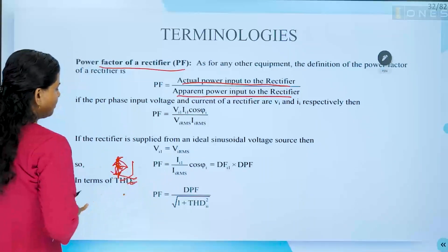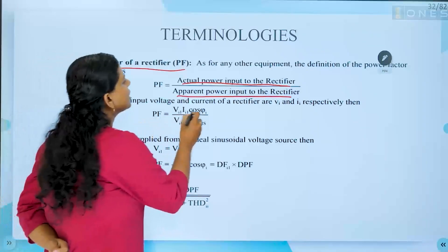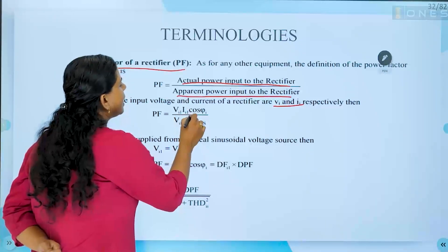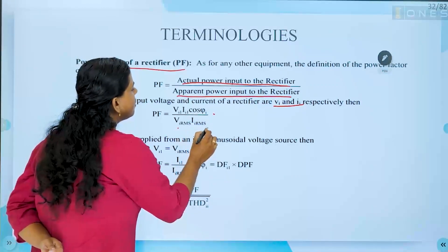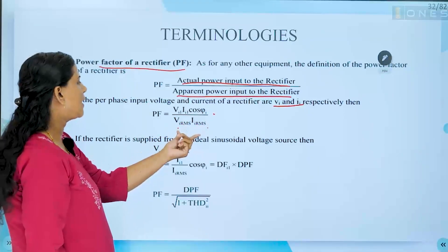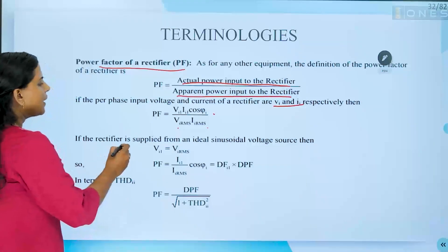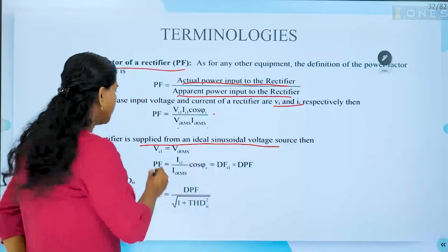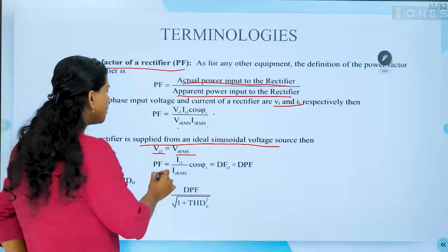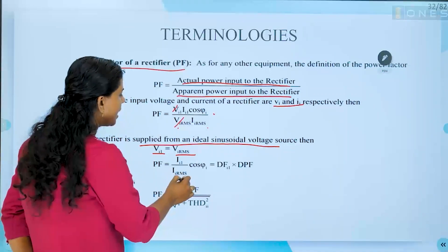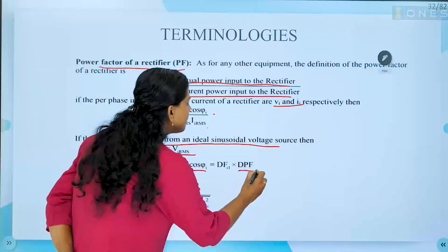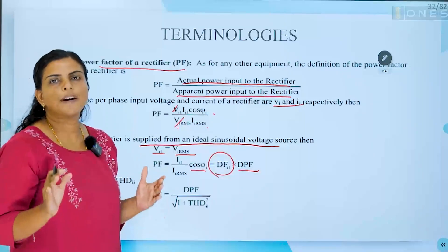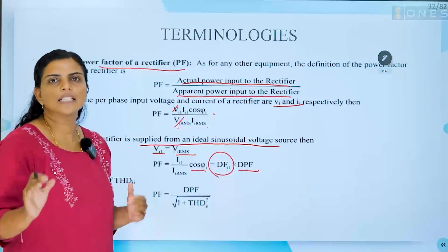Power factor indicates the useful power index. If the RMS input voltage and current of a rectifier are Vi and Ii respectively, then power factor equals (Vi1 · Ii1 · cos φi) divided by (Vi,RMS · Ii,RMS). If the rectifier is supplied from an ideal sinusoidal voltage source, the RMS value equals the fundamental value, so Vi,RMS = Vi1. The equation reduces to: power factor equals (Ii1 / Ii,RMS) · cos φi. Here, cos φi is the displacement power factor, and Ii1 / Ii,RMS is the distortion factor. So in effect, power factor is the product of distortion factor and displacement factor.